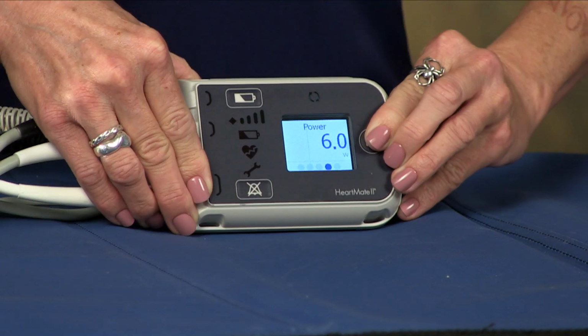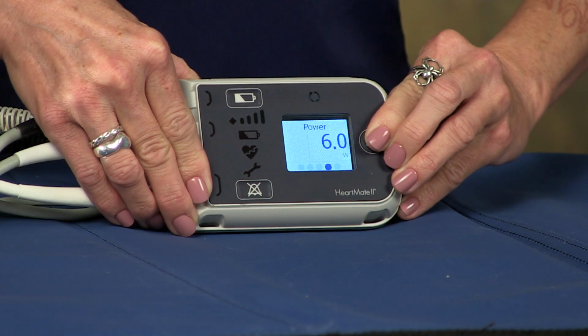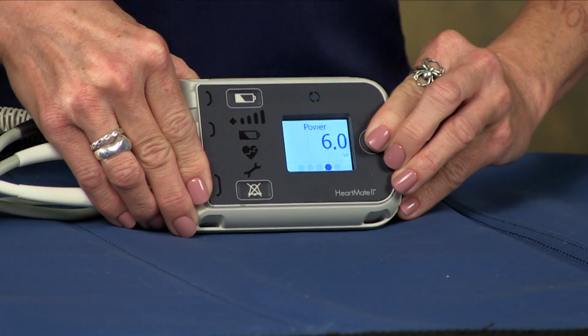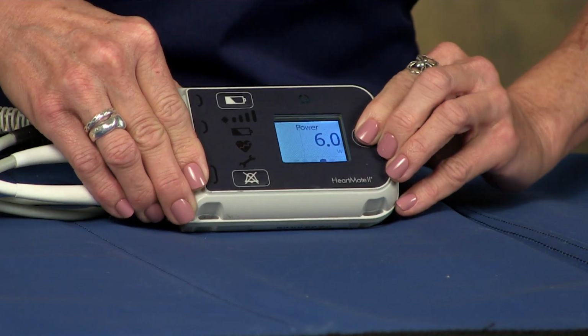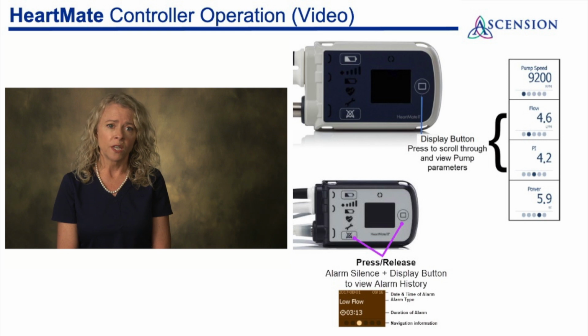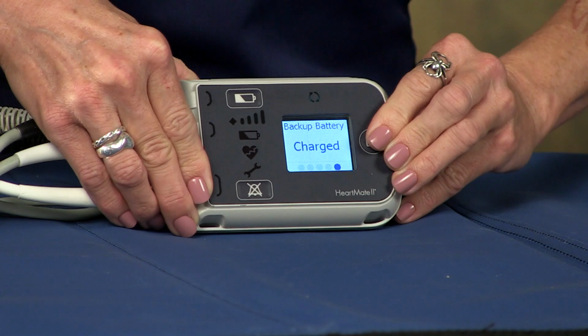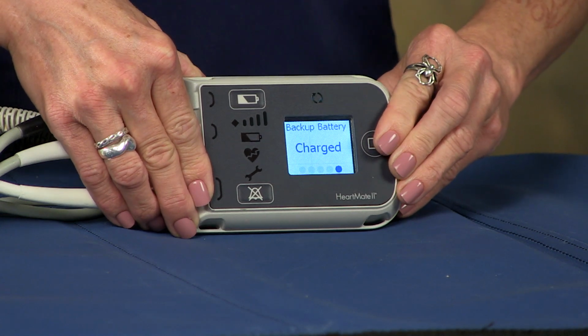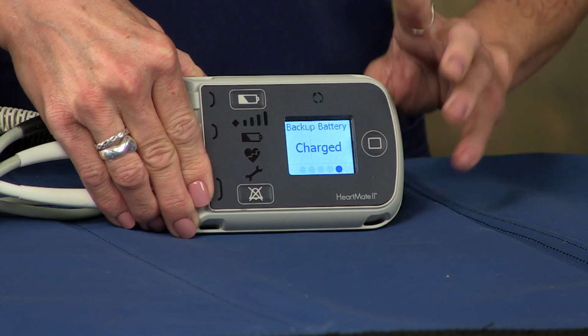Power is needed to run the pump, and it's measured in watts. If the power is 2 watts above the patient's baseline, which they should know, or if it's greater than 10, there may be something wrong with the pump, or there may be an obstruction. This last screen shows the internal controller battery is charging or is charged. This unit does have an internal backup battery for absolute emergency loss of power to prevent the VAD from stopping. We say it's like an airbag. You know it's there, but we don't really want to use it.